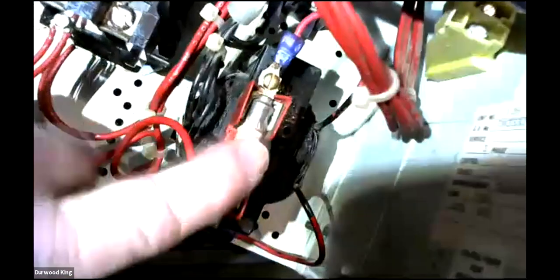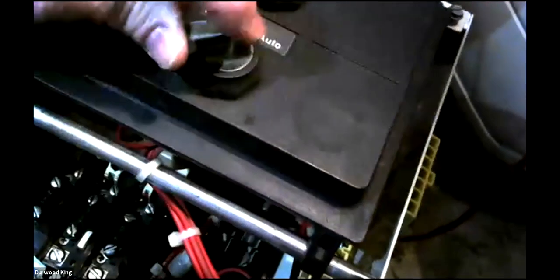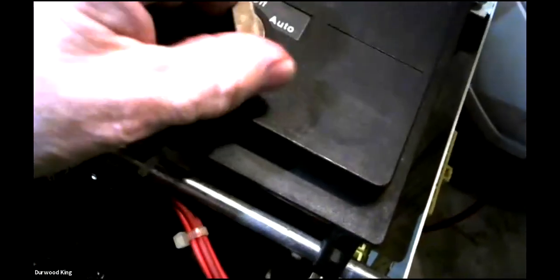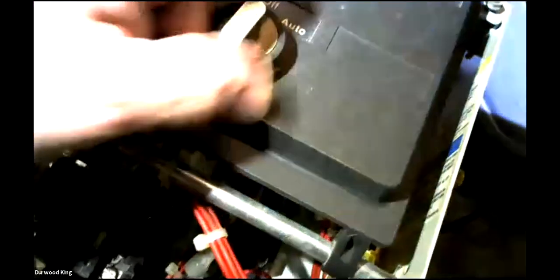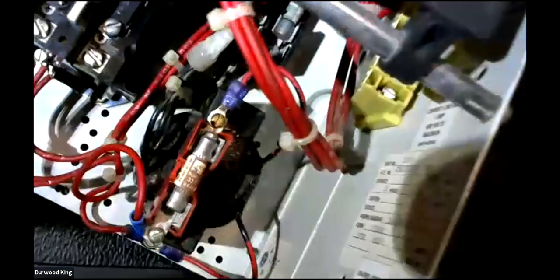So the fuses and all that are in here, they're going to be those dual element time delay. Anything in motor controls are going to be those ones that have a time delay to them. And so this would be actually in there to protect your transformer, which would be for your start stop circuit. That transformer would be in there for your switch. You got your switch here. So if you're going to go in hand, the starter's going to come on automatically. The control power up here for that and that light is going to come from that transformer down there.